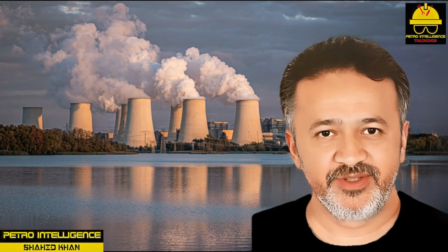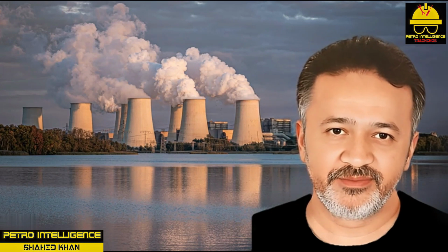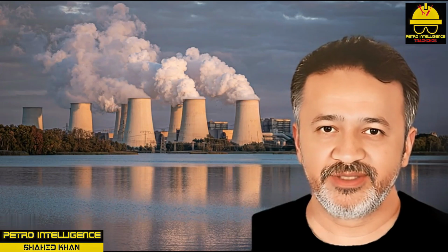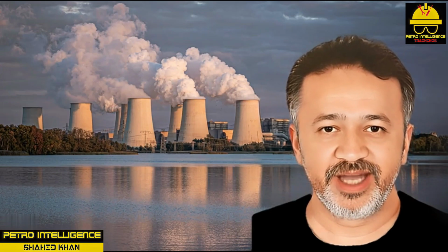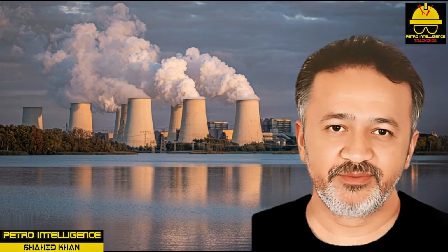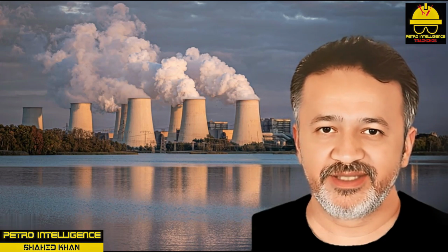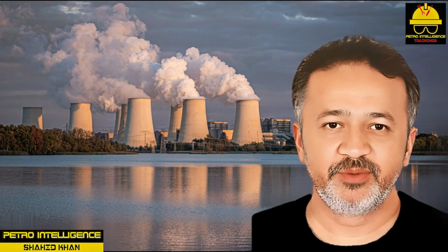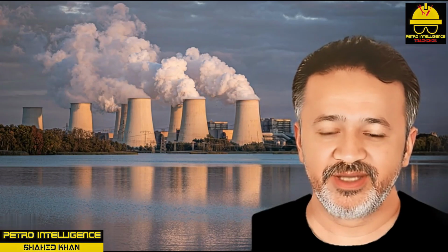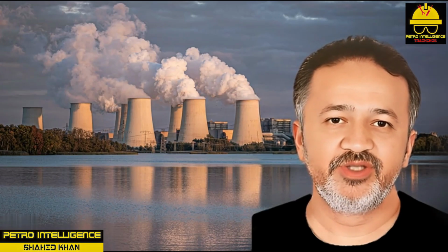Operators check the level of suspended solids frequently. The level of suspended particles is measured in parts per million, ppm, that is, 1 ppm equals 1 pound to every 1 million pounds. The level of suspended solids is then compared against an acceptable standard. The ratio of the actual to the standard level is called the cycle of concentration.